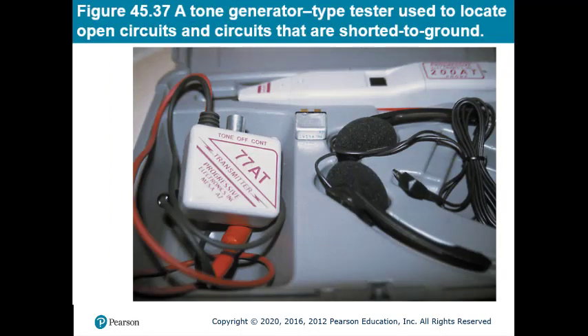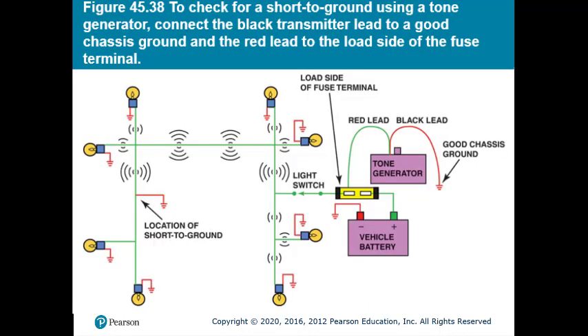There's also what's referred to as a circuit tracer method, or I call it the tone generator. So you put in a device to generate a tone out through the wiring as a transmitter, and then you have a handheld receiver where it'll create a tone as long as there is current flowing through the wire creating the short. You can follow that tone until you find where the short is.